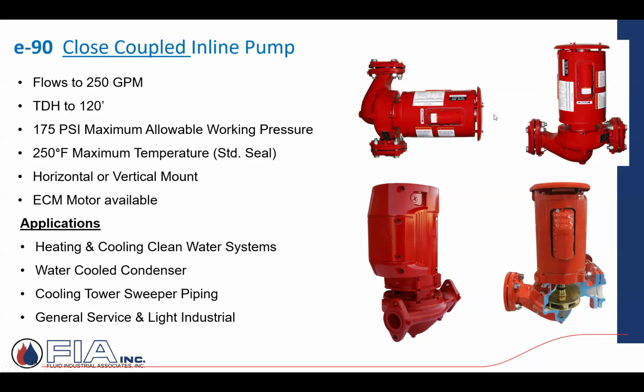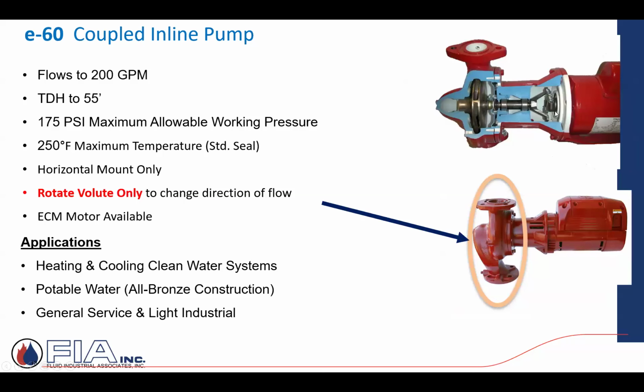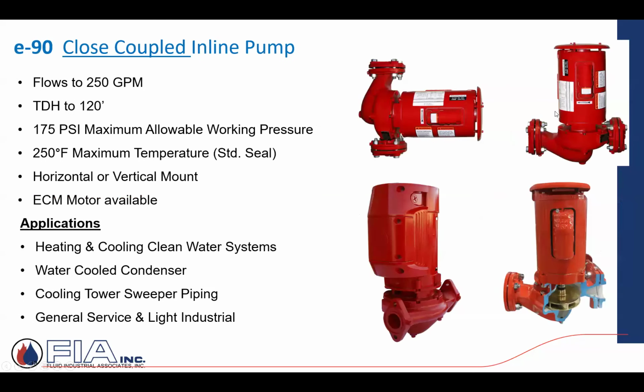And when they say vertical or horizontal, what we're referring to is the orientation of the motor. How does that motor sit? The pump itself can be top to bottom, bottom to top. It can be left to right, right to left. You can change and orient, but you've got to be very specific, which way is the motor. In this case here, this E90 is pretty flexible. It can go either way. The 60 always is inline, never vertical.